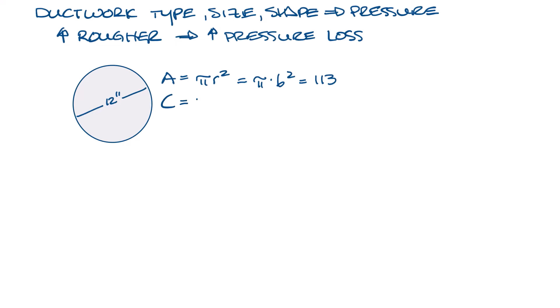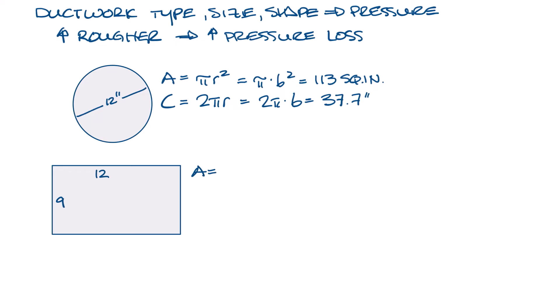The surface area is 2 pi r, so if we do the math here, that's 37.7 inches. Whereas a 9 by 12 ductwork would be about the same area of 108 square inches, but its surface area or its perimeter is going to be 42 inches. So the closer to round, the lower the loss.